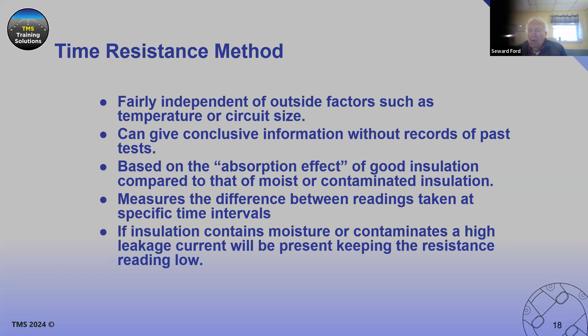But based on the absorption effect of good insulation compared to that of moist or contaminated insulation, you get different readings. Measure the difference between readings taken at specific time intervals. Specific time intervals. Again, we have that important point. If insulation contains moisture or contaminants, a high leakage current will be present, keeping the resistance reading low.